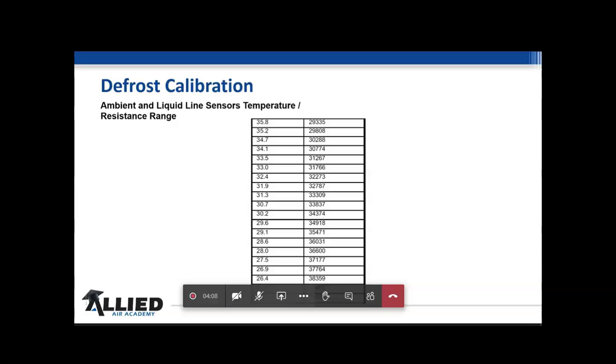I snipped this out, the ambient and liquid line sensor temperatures. I snipped this out to show 35 degrees down to 25 degrees. And if you look at the ohms rating here, so it's a 10K ohm resistor, but it's a 10,000 ohm difference just between 10 degrees. So when we're out there looking at these and when we're talking to contractors working on these things, it is highly important for them to understand that we need to be somewhat within this range. But I also found what happens if these sensors mess up, what algorithms are in the board if these sensors mess up. And I found it to be very interesting when I found it, and I want to share that with you today as well.